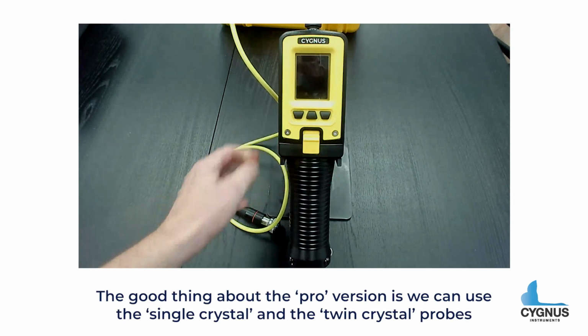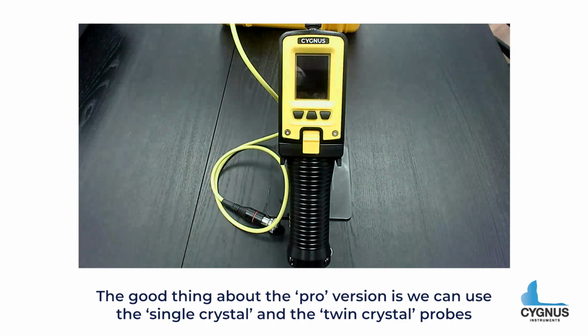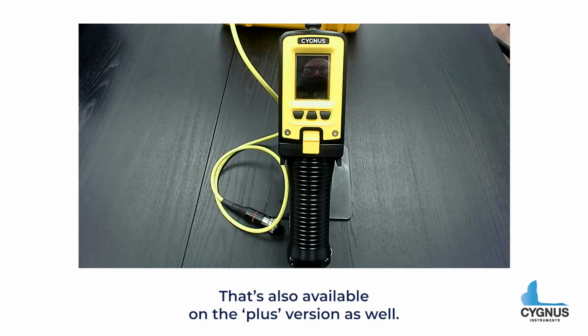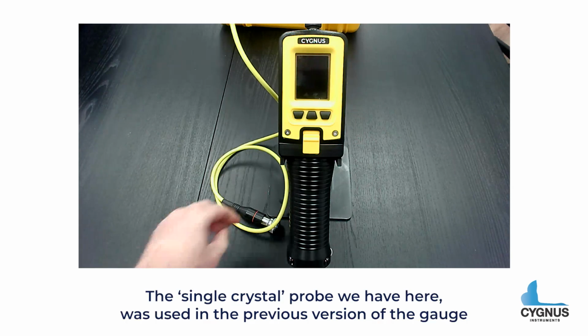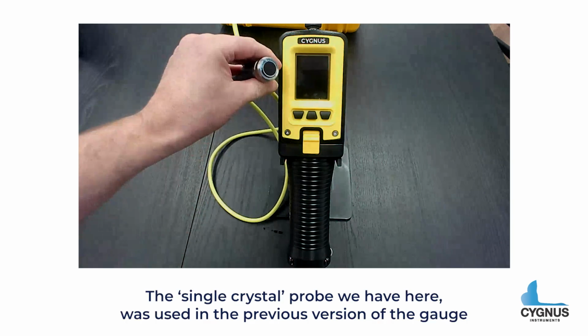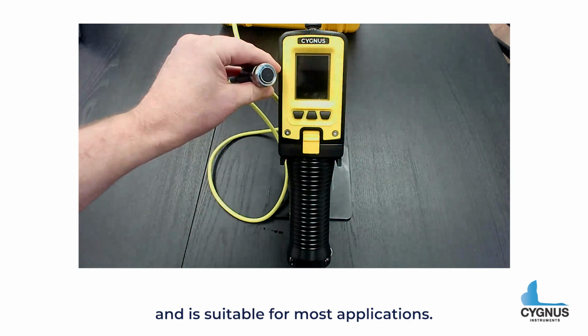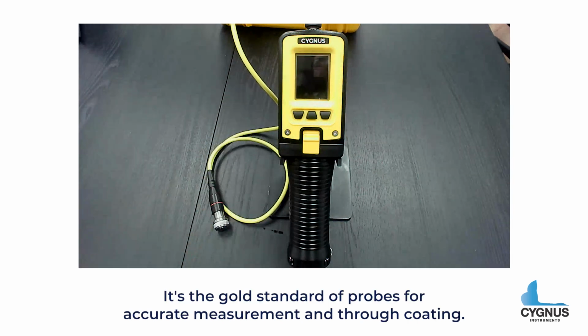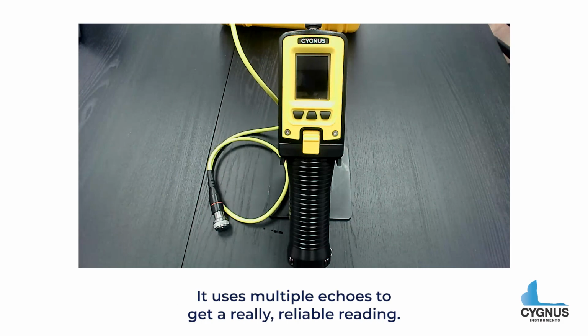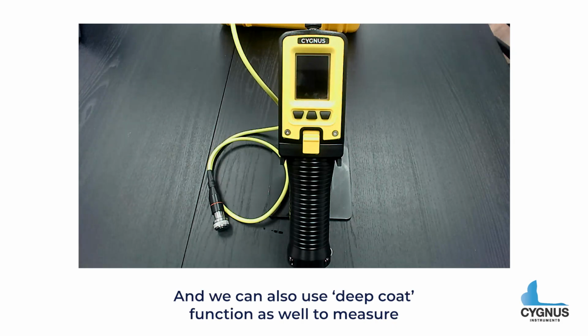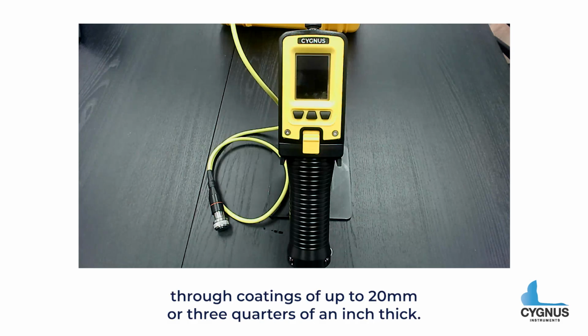The good thing about the Pro version is we can use the single crystal and the twin crystal probes. That's also available on the Plus version as well. The single crystal probe we have here was used in the previous version of the gauge and is suitable for most applications. It's the gold standard of probes for accurate measurement and through coating. It uses multiple echoes to get a really reliable reading, and we can also use the deep coat function to measure through coatings of up to 20 millimeters or 3/4 of an inch thick.